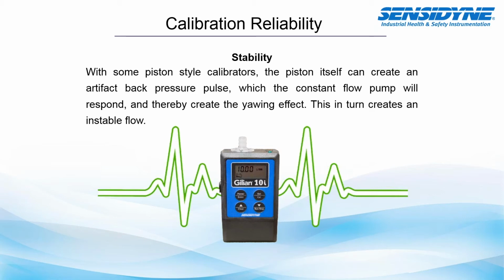Now, with some piston-style calibrators, the piston itself can create an artifact back pressure pulse, which the constant flow pump will respond to and thereby create the yawing effect. This in turn creates an unstable flow. So let me talk about this artifact.